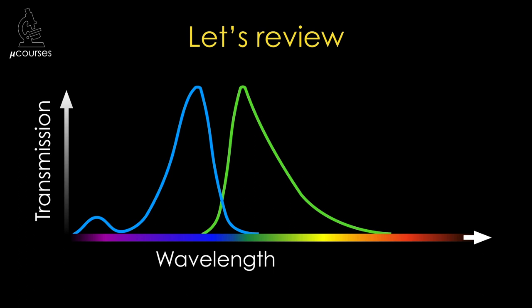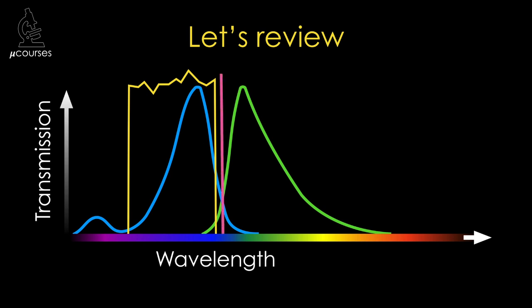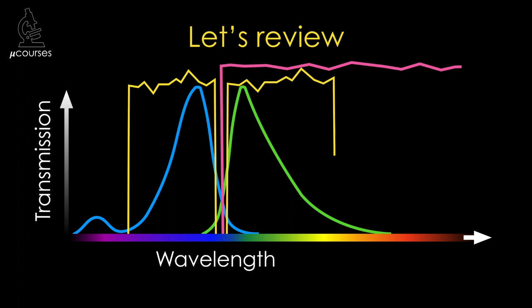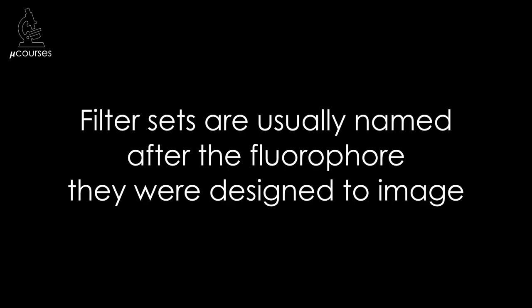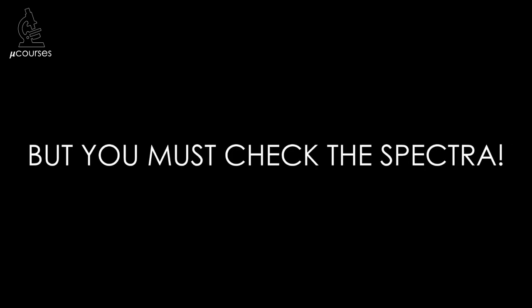Let's review what we've learned. An excitation filter should be chosen that transmits the peak excitation wavelengths. A dichroic beam splitter should be chosen that reflects the excitation and transmits the emission. An emission filter should be chosen that transmits the peak emission light. Filter sets are usually named after the fluorophore they were designed to image, but similarly named fluorophores can vary in their spectral properties, so you must always check the spectra.